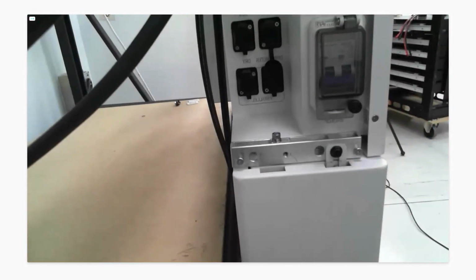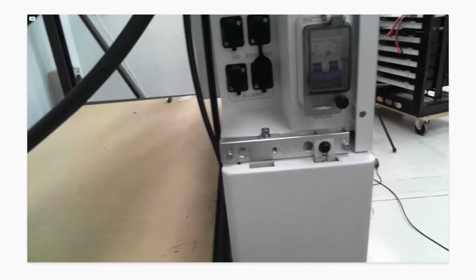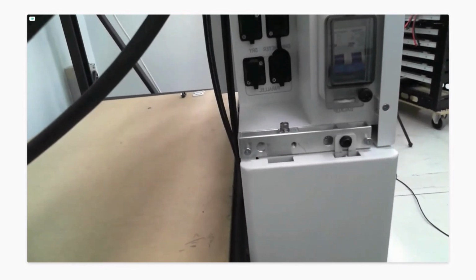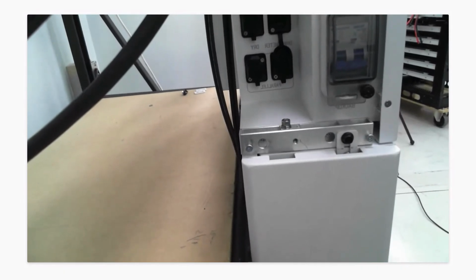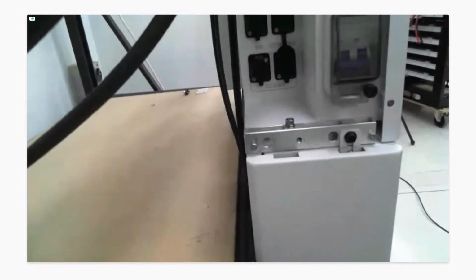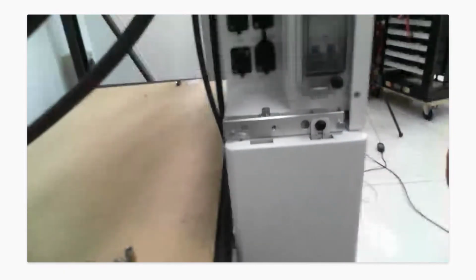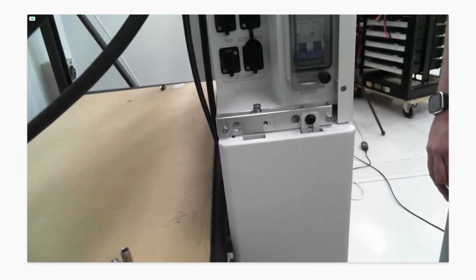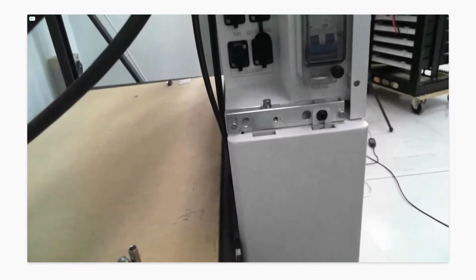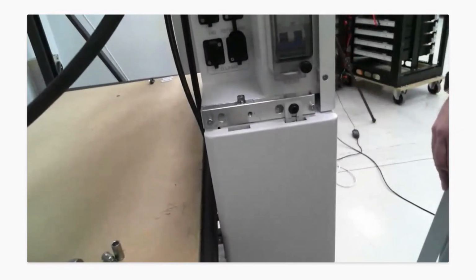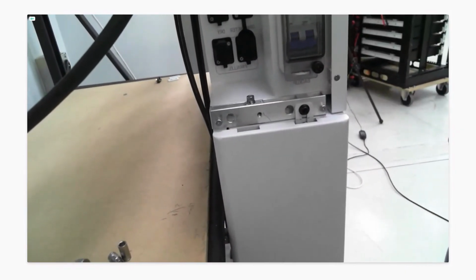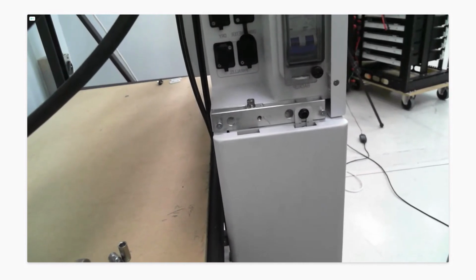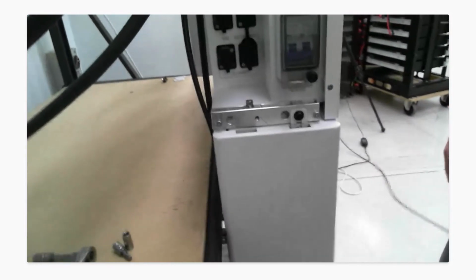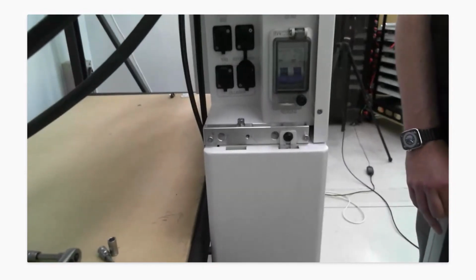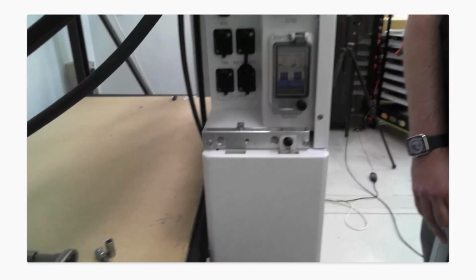Well, the previous standard or installation behavior for most installers was that the PV earth would run down to the inverter. From what I've heard from installers, it may have changed so that the PV earth needs to run directly to the meter box now. But we still have this earth connection in place. I mean, we are earthed through the AC cable as well. That's the normal PE, and this is sort of the chassis PE. So check your standards, installers, and make sure you're getting it all tickety-boo.